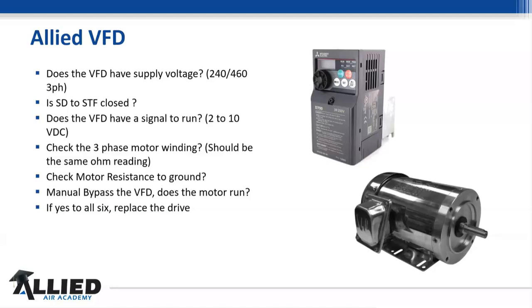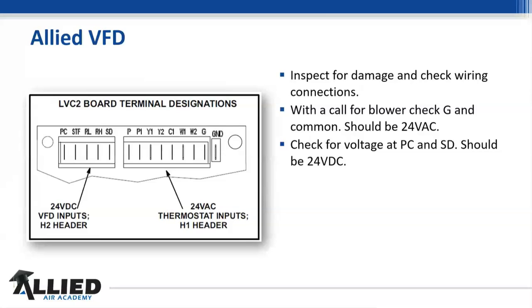And you want to check the motor to ground, and then you can manually bypass the VFD to make the motor run in certain situations. If the VFD is going down or not acting right, you can bypass it until you get it fixed. We don't want to do that all the time because you take your efficiencies and all that out. But if all these things are good to go, you're probably going to need to replace the drive. But before we replace this drive, let's take a look at the board itself.